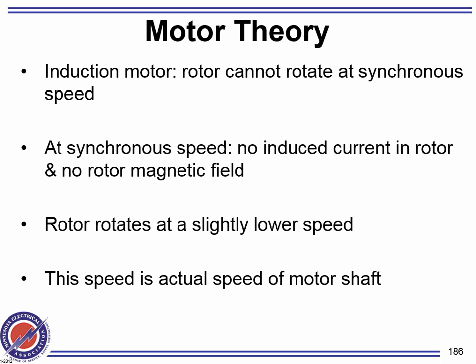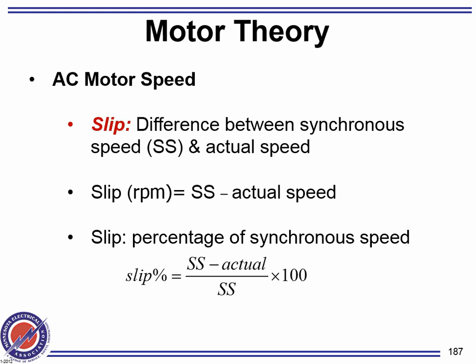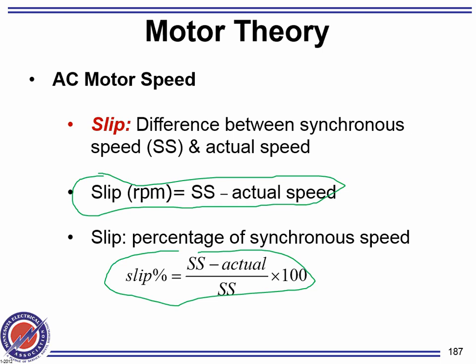So no current, no rotor. If you run them at synchronous speed, there will be no rotor current induced, and so forth. Let's go into slip. The rotor itself typically runs slightly behind the synchronous speed, typically 3 to 5, 6% behind it, and that's how you get torque out of the machine. That's called the slip. Slip percentage is the slip divided by the synchronous speed. How far is the actual speed of the rotor from the theoretical speed of the magnetic field? So please remember that one too. These are the things you need to know first about motors. Basically, these formulas, this one, and these two.